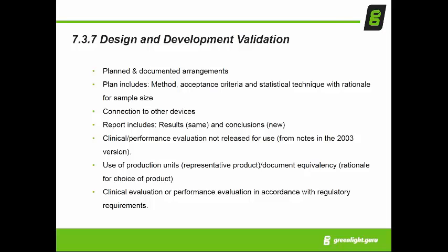Clinical evaluation is very much a design and development validation type of activity. And so there's a much heavier emphasis on the need for conducting some clinical evaluation as it comes to demonstrating your product meets your user needs. And so this clause in the 2016 version of the standard has become much, much beefier as far as the expectations and the requirements are concerned.